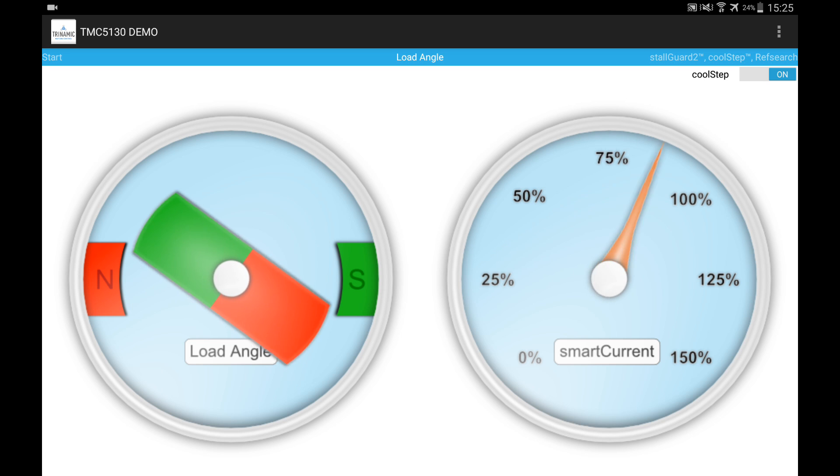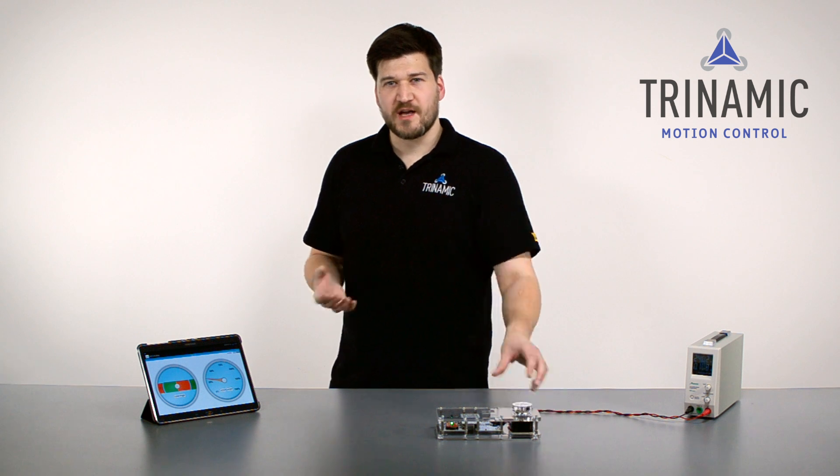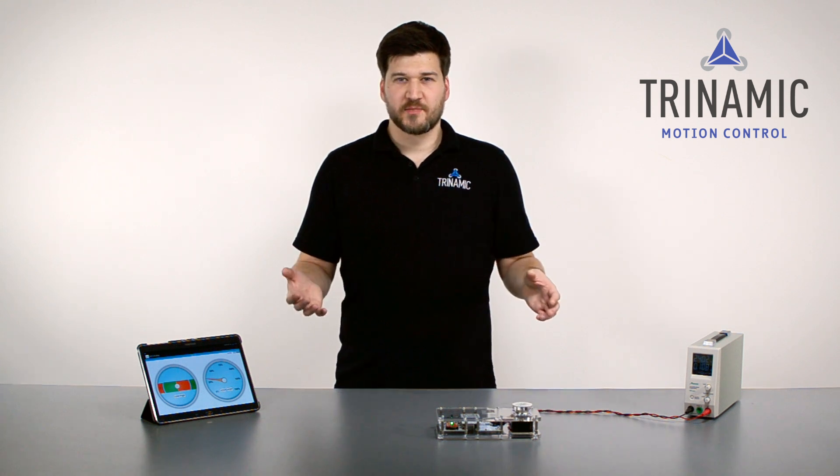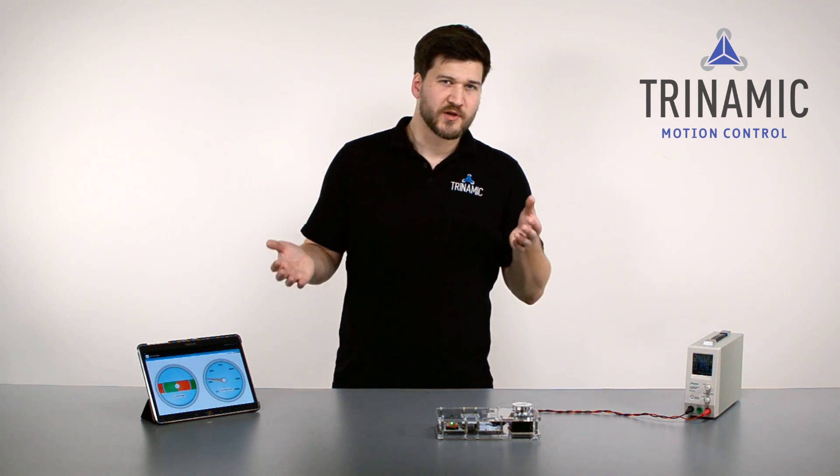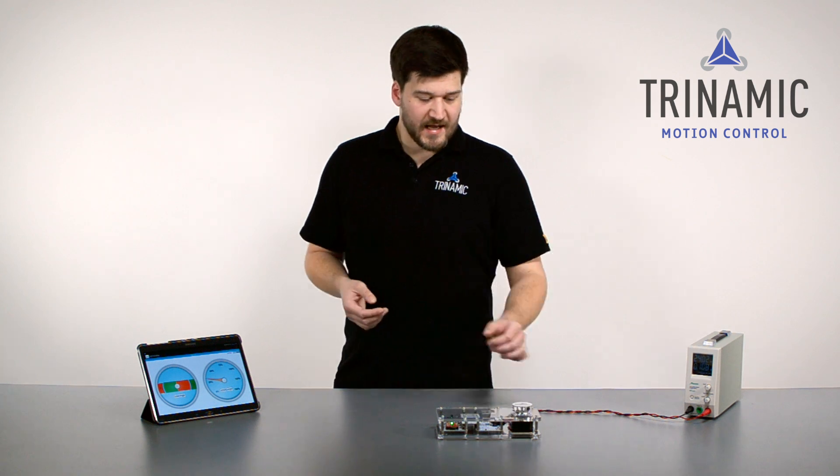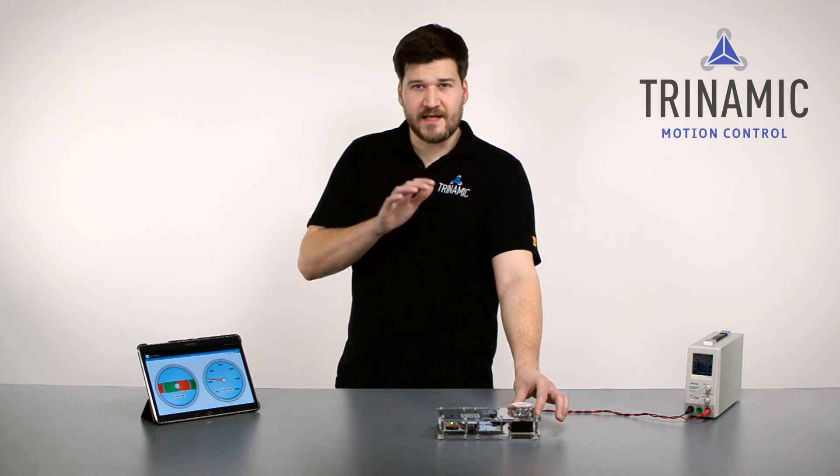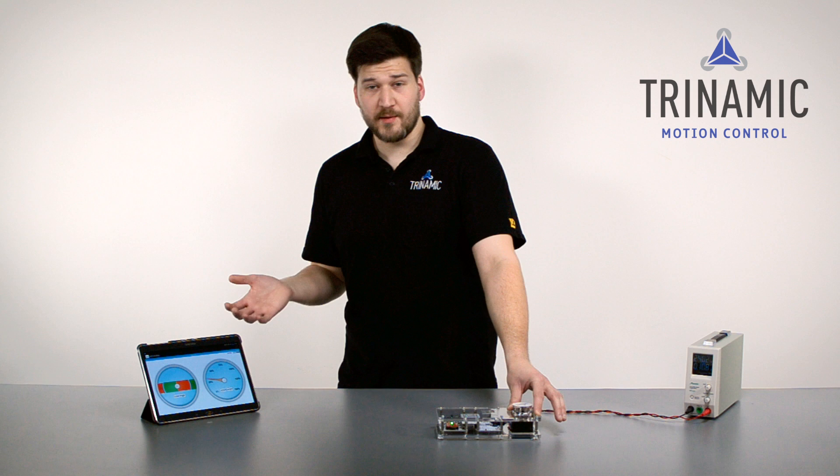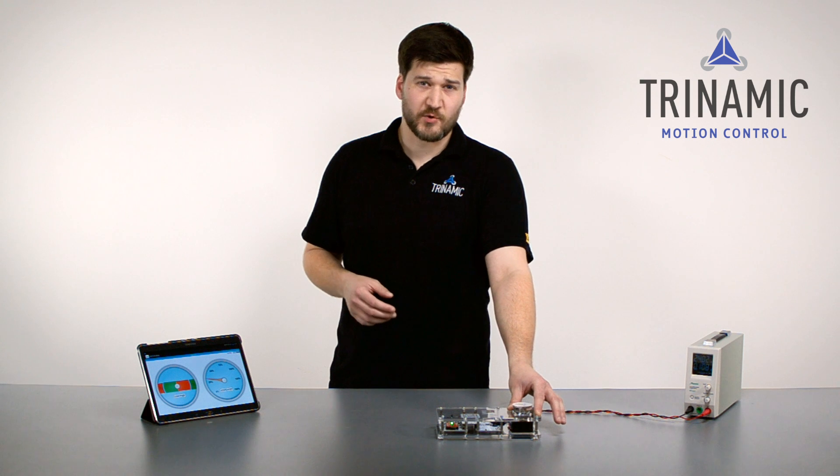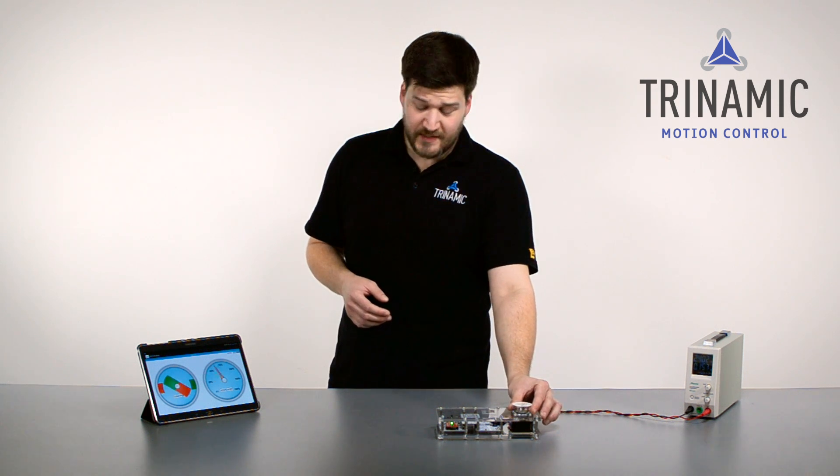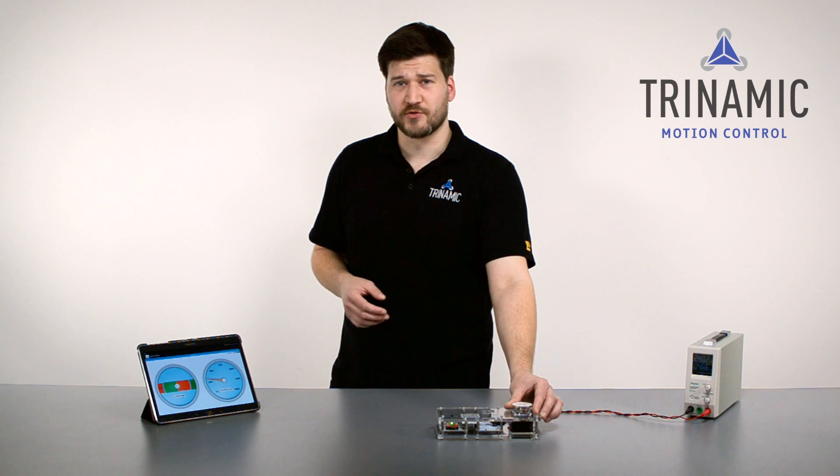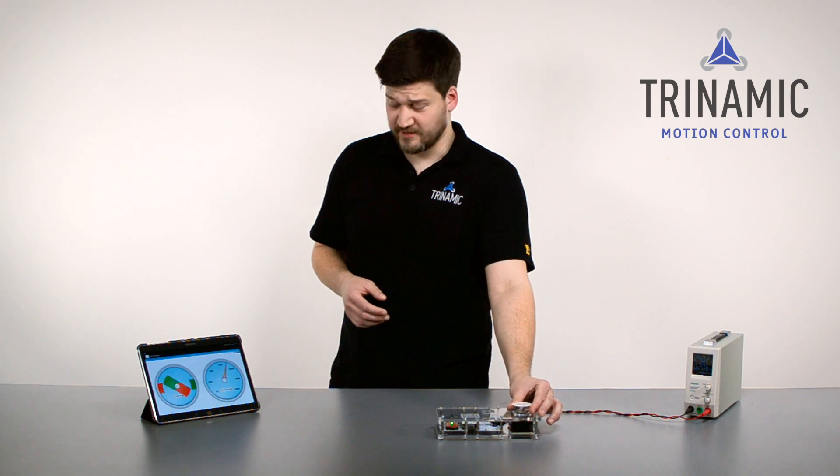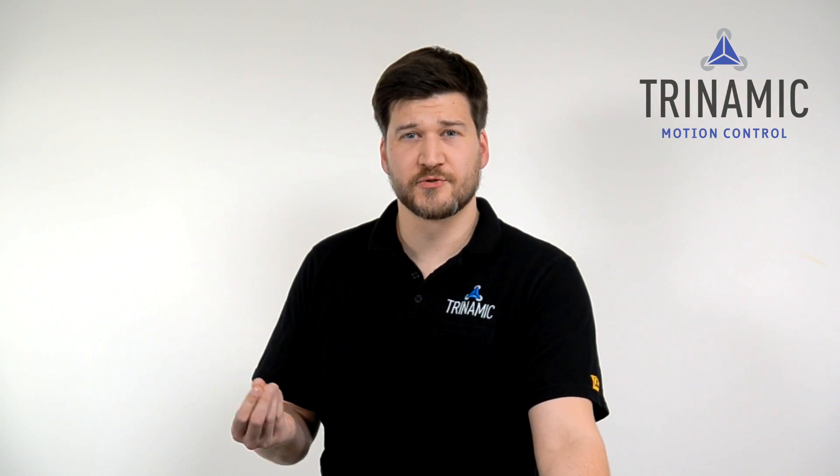And this is pretty nice. Normally you would over-dimension a stepper motor a little bit, like let's say 1.2, 1.5 times, something in this range. And with StallGuard and CoolStep, you can think about taking a smaller motor and the good thing is you can over-boost the motor a little bit. For a short time the motor will be able to get a little bit more torque out of the system.